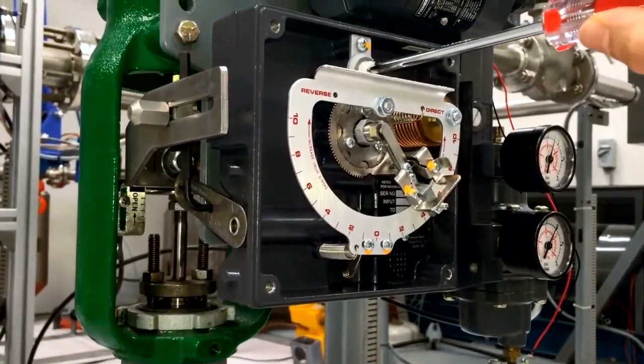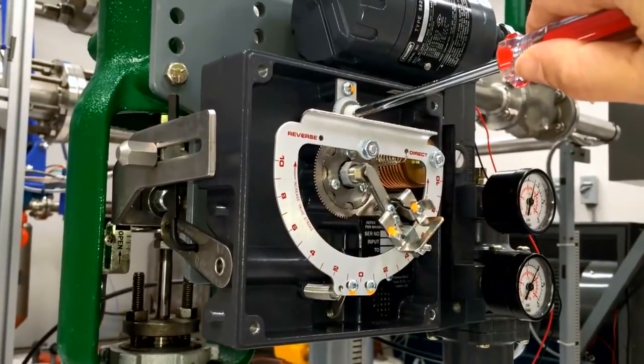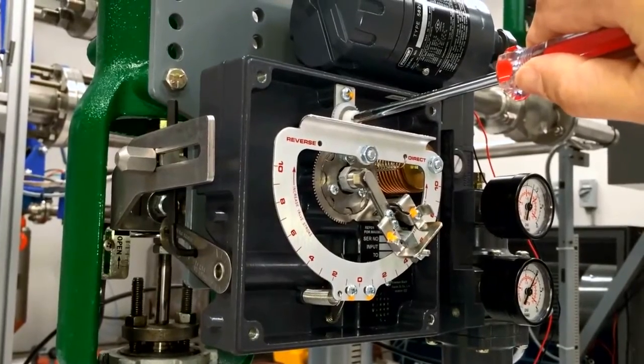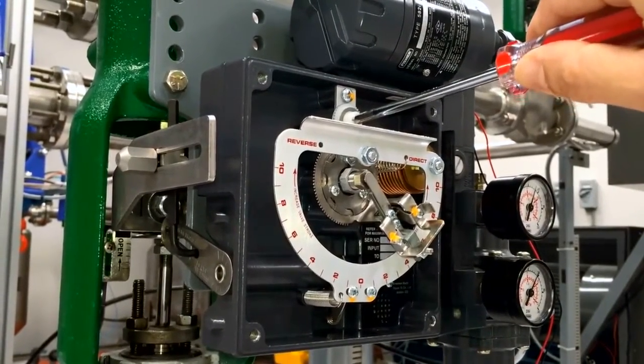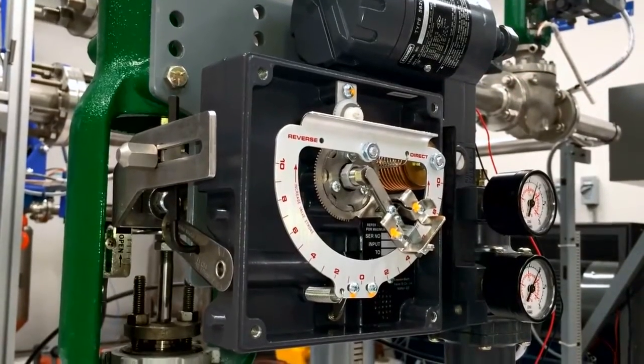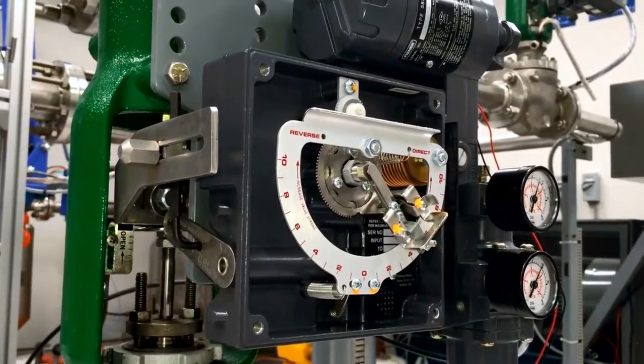The actuator stem should be at the expected travel. If the stem travel is short of its expected range, increase the travel by moving the flapper assembly to a higher number on the beam, and vice versa to decrease the travel.